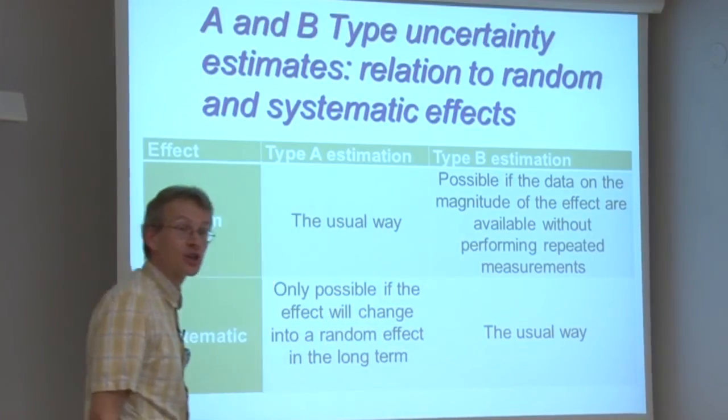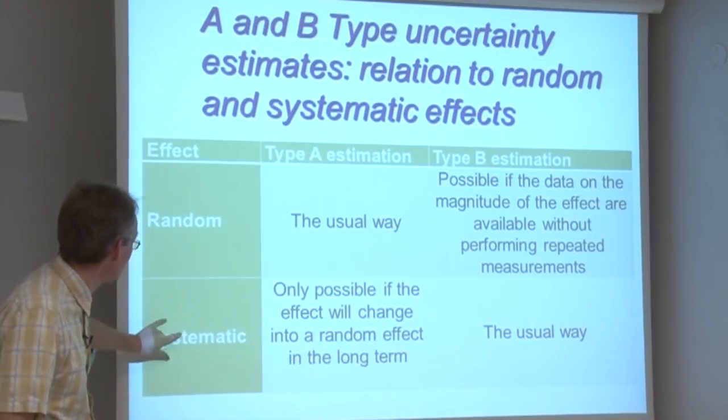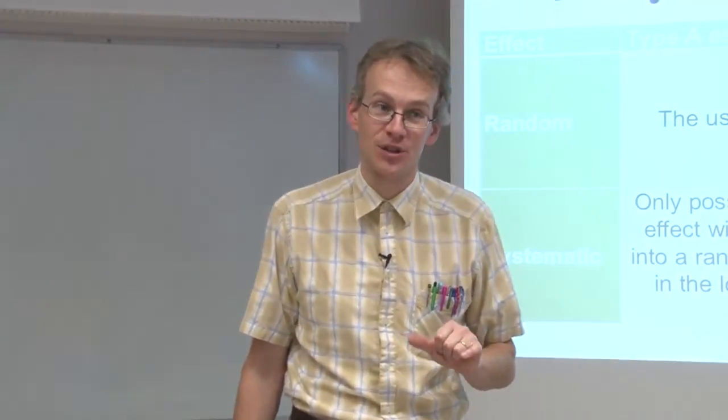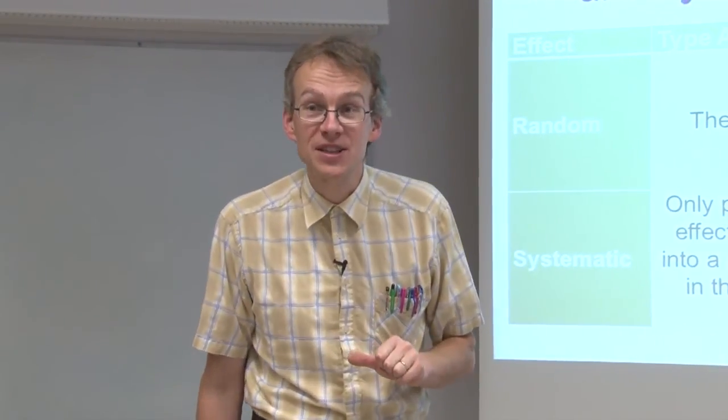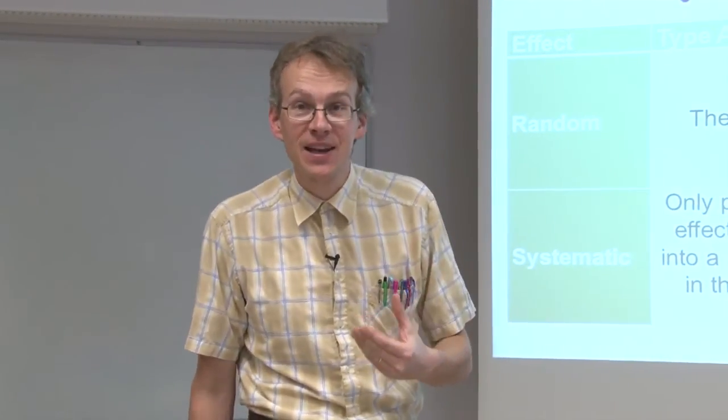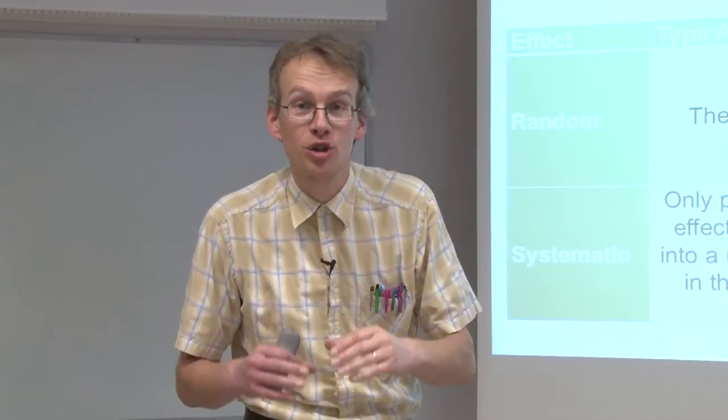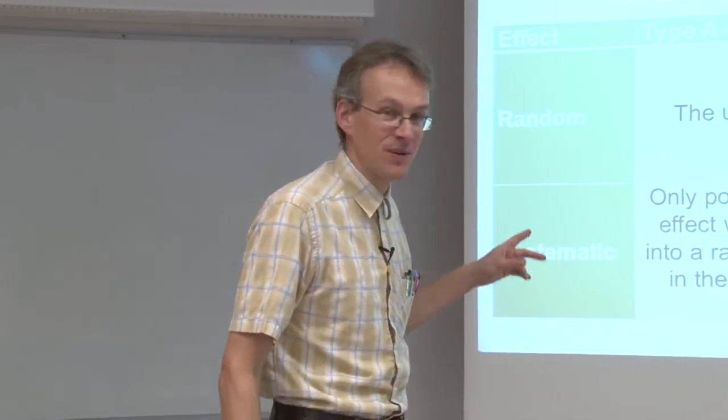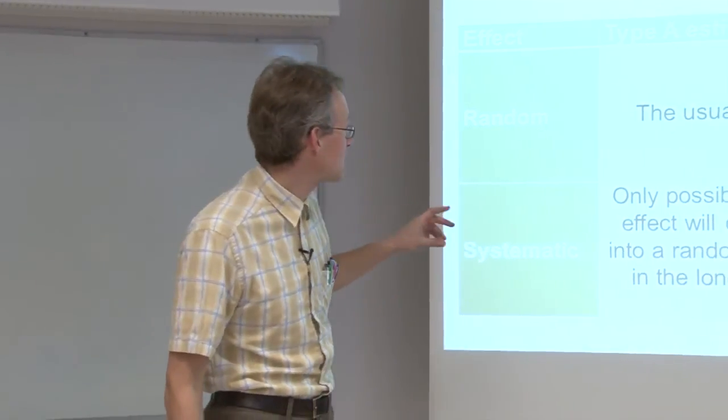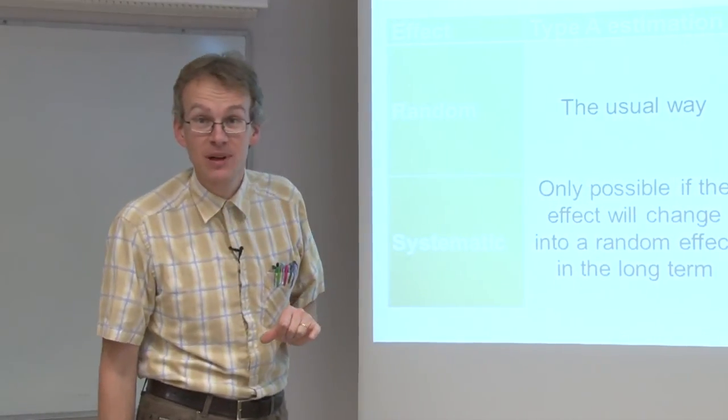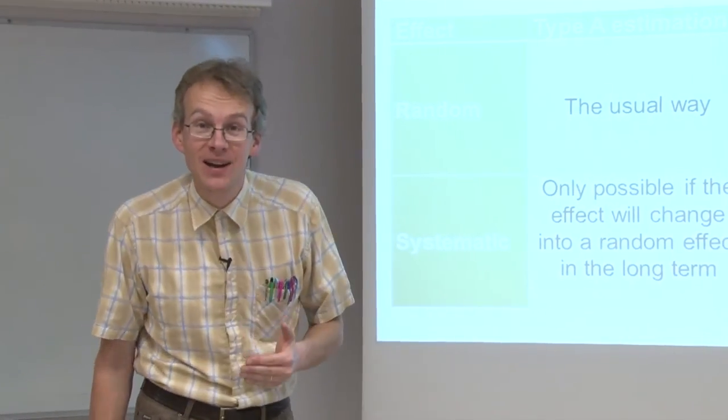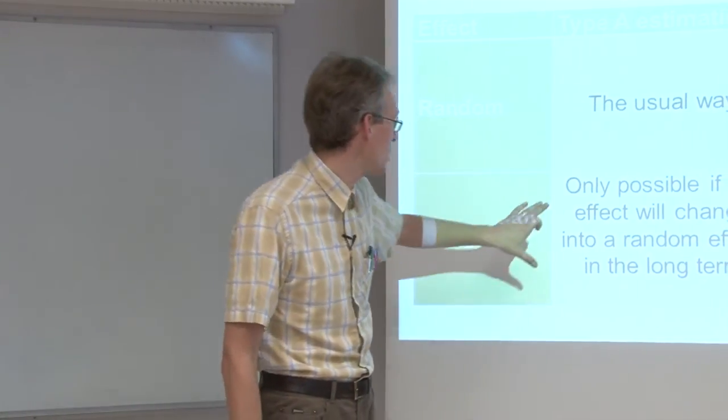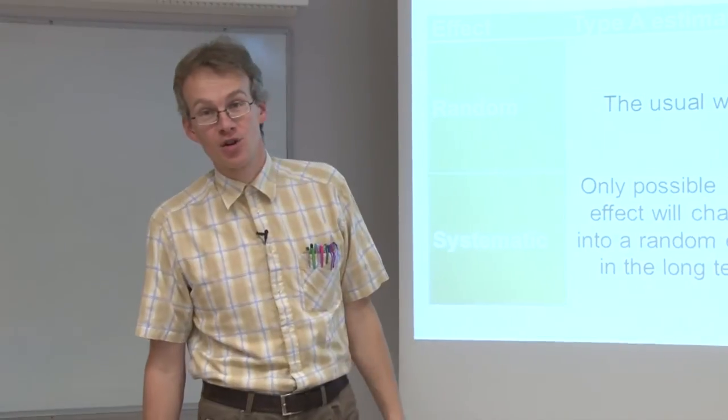However, in certain cases, certain systematic effects can also be evaluated by type A uncertainty evaluation. And these are all those cases where the effect is a systematic effect in the short term but in the long term can become a random effect. In such a case, type A evaluation is possible, and this is what is typically done in within-lab long-term reproducibility calculation, which we see later on in this course.